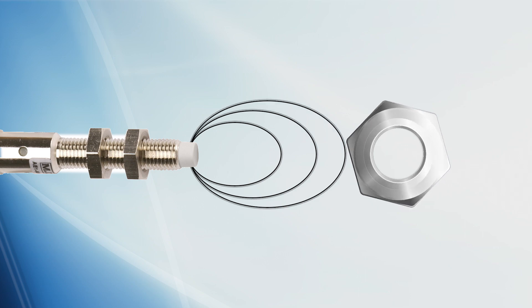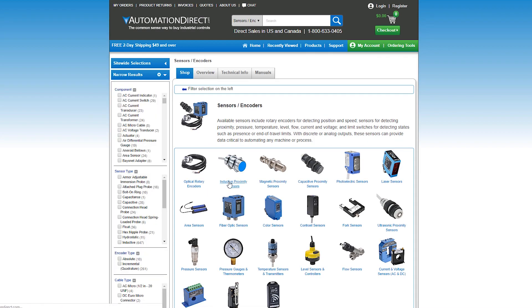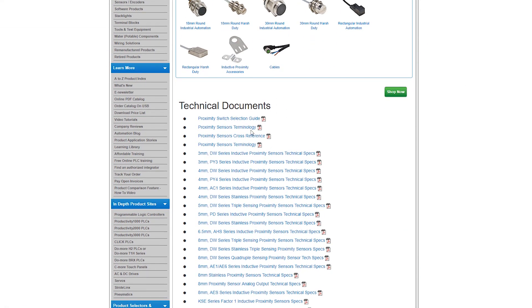Here are a few examples of the metals an inductive proximity sensor will detect: iron, brass, aluminum, copper, and stainless steel. Iron is the most common target. Other metals will have a derating, meaning the target must be closer to the sensor in order to detect. The material correction factors are published for the sensors on AutomationDirect's website.